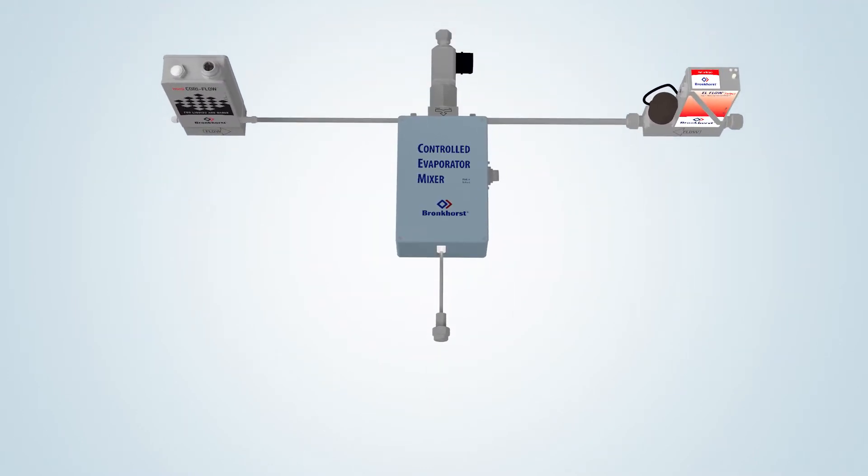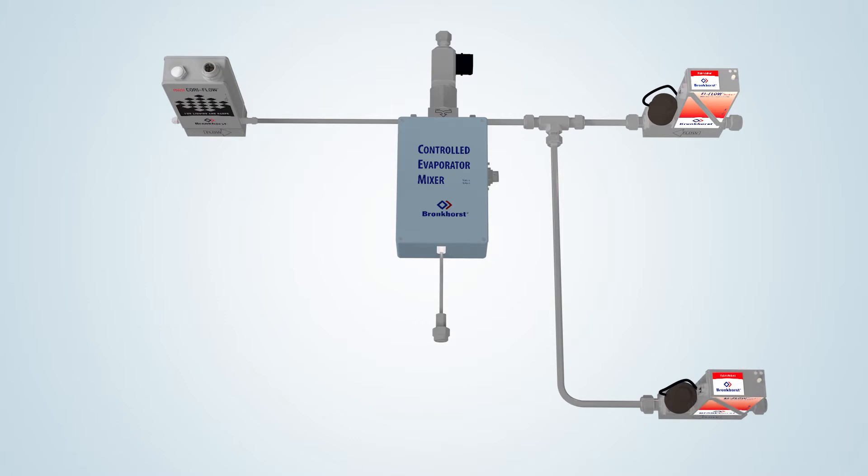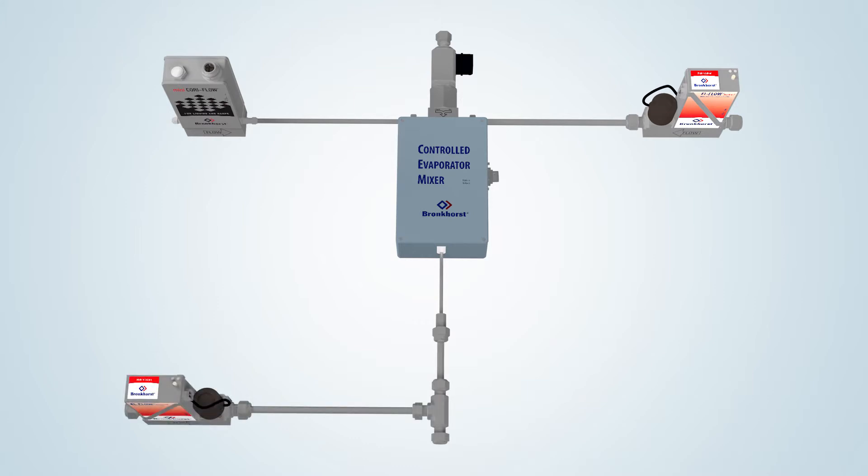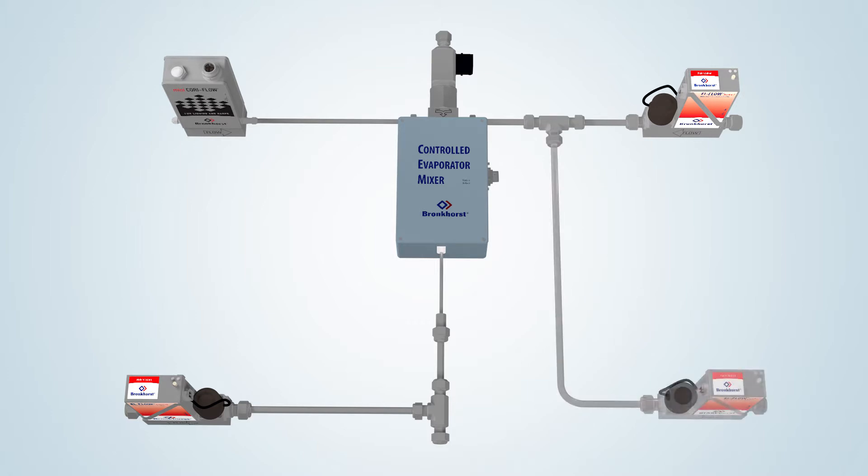Using the CEM module, vapor flows within the range of 50 milliliters per minute up to 10 liters per minute can be generated for use in atmospheric or vacuum processes. The standard CEM configuration comprises one liquid flow meter and one gas mass flow controller, or MFC. The evaporation module can, however, be equipped with an extra MFC for dual carrier gas supply. Another option is to dilute the outflowing vapor by adding an extra MFC at the outlet, and of course these two options can also be combined.